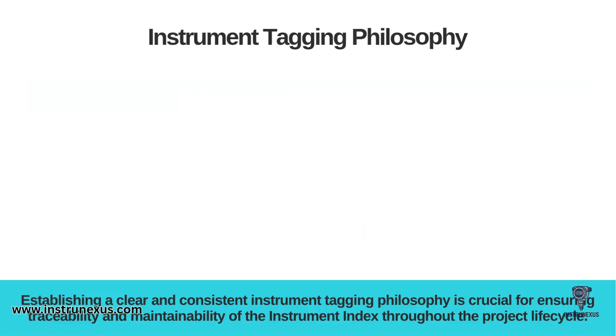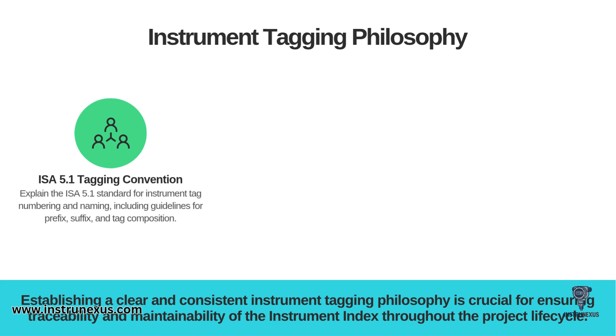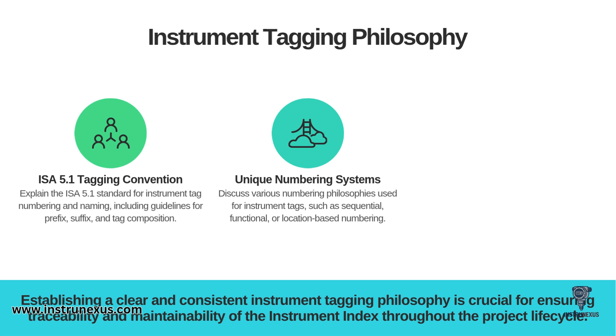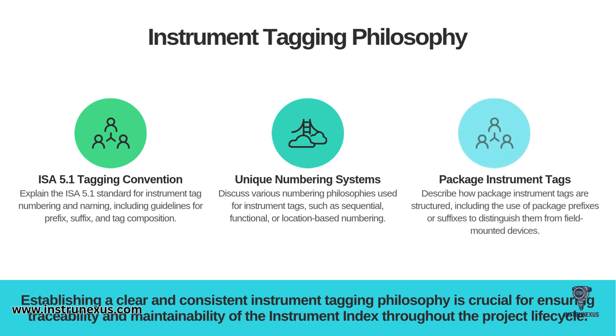A key part of the index and the project specification is the instrument tagging philosophy. You can't just make up tag numbers. The most common standard you'll use is the ISA 5.1 tagging convention, which provides clear guidelines for how to compose a tag — including its prefix for the measured variable, its suffix, and its functional identification. Within that standard, projects might adopt different numbering systems: sequential, functional, or location-based. A special challenge is package instrument tags — instruments that come on vendor skids — where you need a clear philosophy, often by adding a package prefix or suffix to distinguish them from field-mounted devices.